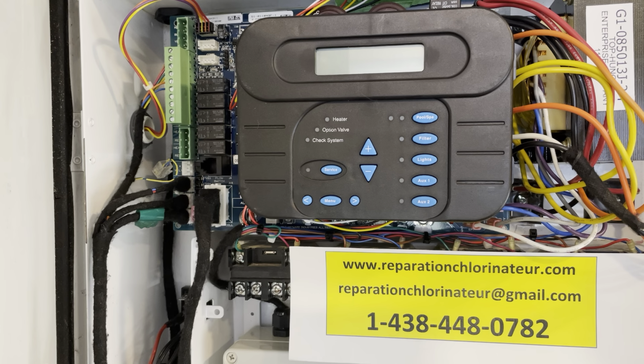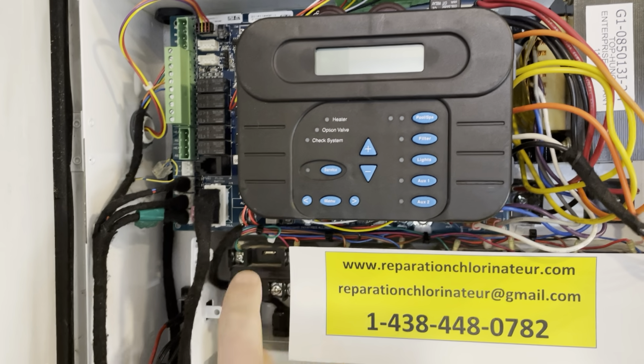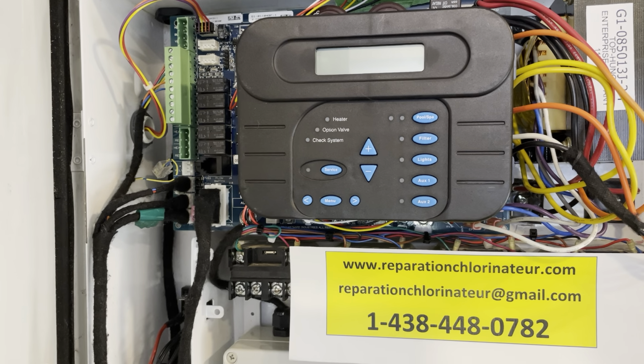If you have a variable speed pump, then maybe it's connected here. Normally it should not. It should be powered directly from the breaker, but sometimes it also needs to be bypassed. If it's connected to the main breaker, then it's a matter of seeing if that variable speed pump can be controlled locally on the pump or not. So it will depend on the pump model.